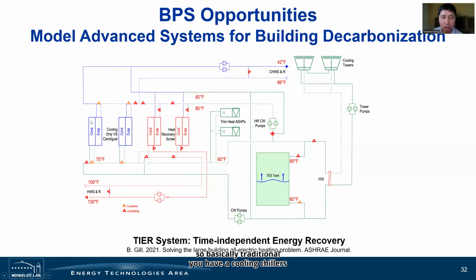Traditionally, you have cooling chillers, which dump heat through a cooling tower, and then hot water boilers. But this new system relies on the conventional chiller plus a heat recovery chiller, an air source heat pump, and a thermal energy storage tank. The tank takes the condenser water heat and stores it, and the heat recovery chiller boosts hot water from 100 degrees Fahrenheit to 130 degrees Fahrenheit.